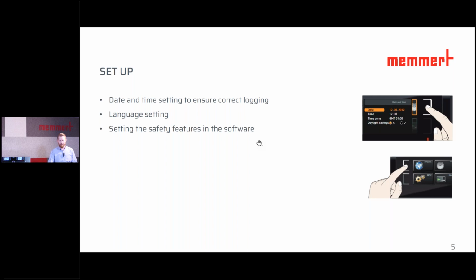It's important to check the time, because data are recorded from startup. If the time is not set at the beginning and only at a later point in time, there may be inconsistencies in the documentation which cannot be corrected afterwards. In addition to the language settings, which can also affect the documentation, many devices offer the option of making basic security settings. These should also be set directly upon commissioning.